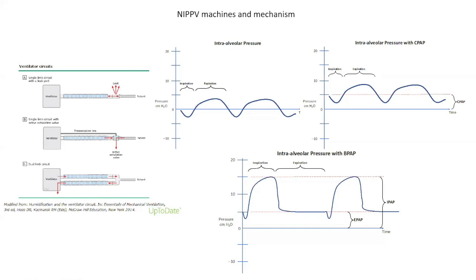The advantages to using non-invasive ventilation off of a standard ICU ventilator are that you can generate higher flow rates and have better alarm systems. The dual tubing actually helps to minimize the risk of rebreathing carbon dioxide. The top two examples are more like portable ventilator circuits that you may see commercially available. You could use them at home. These have more limited flow rates, and the single limb tubing does create a higher risk of CO2 rebreathing, just something to keep in mind.